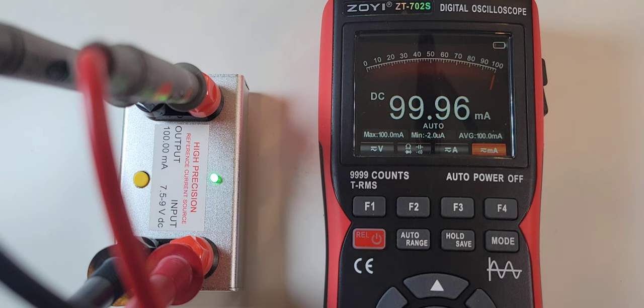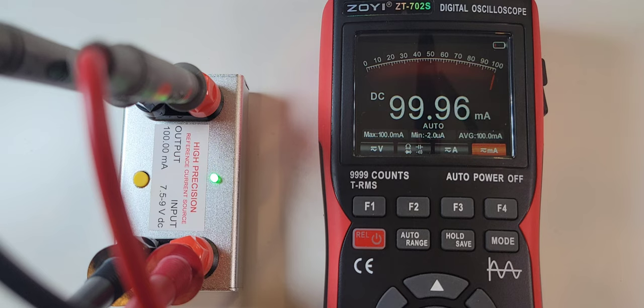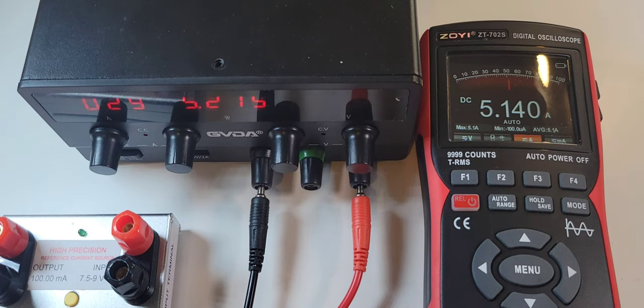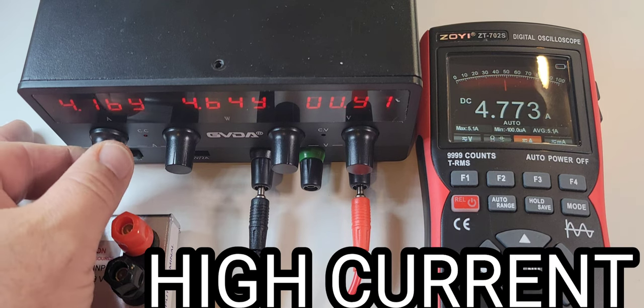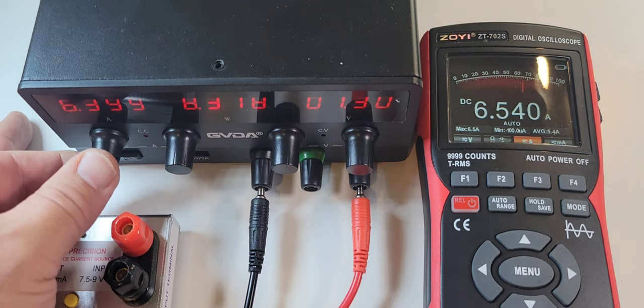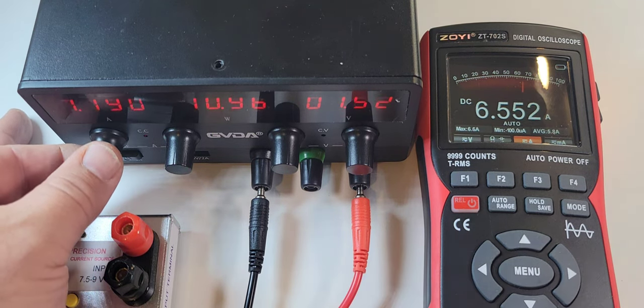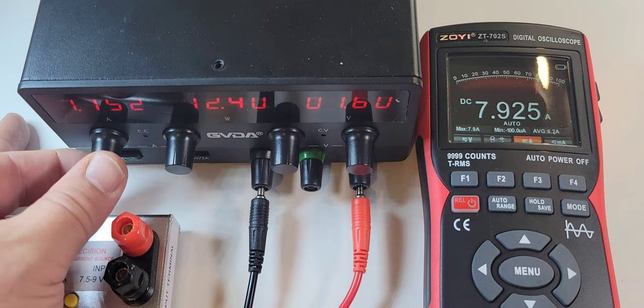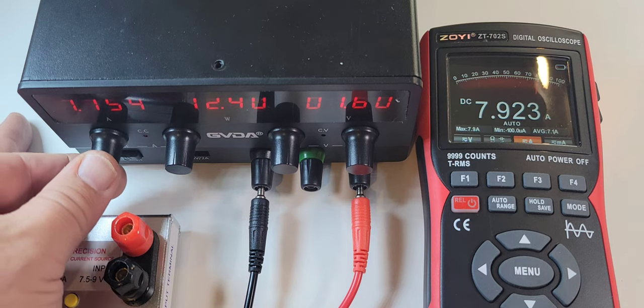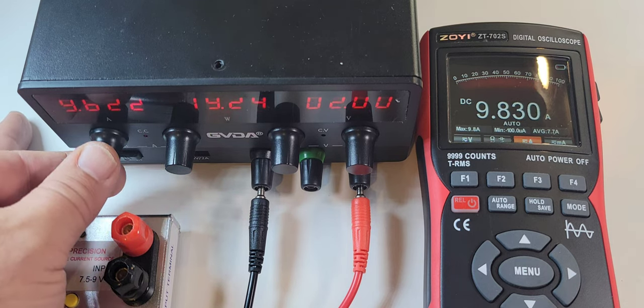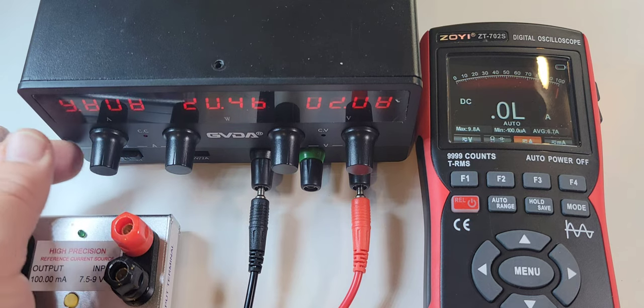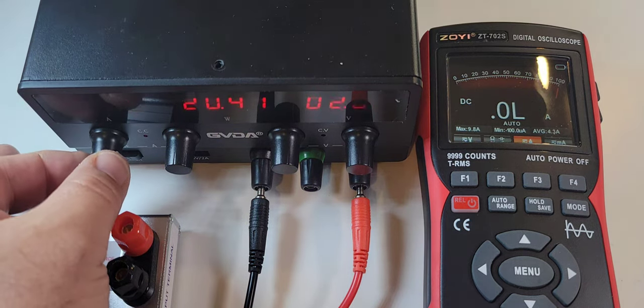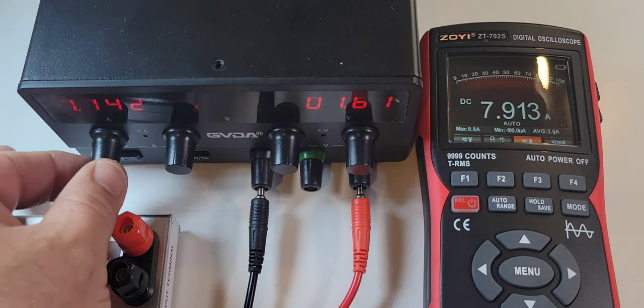And we were hooked up to that current reference, 100 milliamps coming in at 99.96. Now in high current sitting at 5 amps right now, let's bring it up. 6.3 amps coming in at 6.5. 7.75, 7.9, so a little high. 10 amps we're getting that high current alarm, bring it back down.